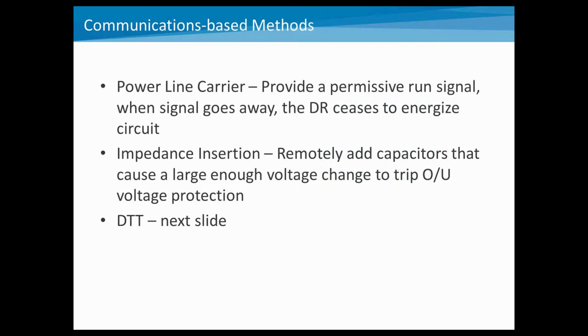So as we move on to communication-based methods of anti-islanding, there's a variety that we'll talk about quickly. First, power line carrier. And typically this is employed where you use a permissive run signal at all times on the grid. And then when the signal goes away, the DR recognizes that and ceases to energize the circuit. There's things like impedance insertion, where you may have a capacitor bank located near your DR that's remotely controlled, and if you go into an island condition, then you can add those capacitors and cause the over-under voltage protection to activate. And then one that's also used quite a bit, especially for larger scale systems, is what's called direct transfer trip, and we'll talk about that on the next slide.